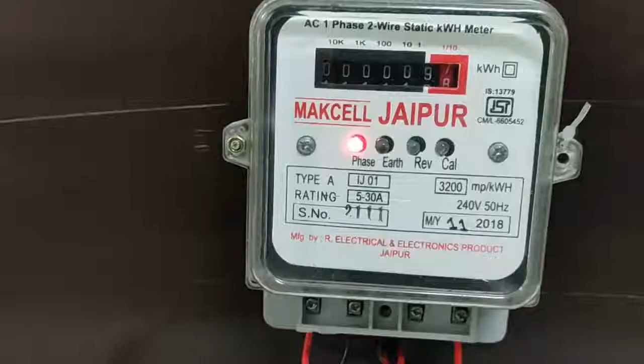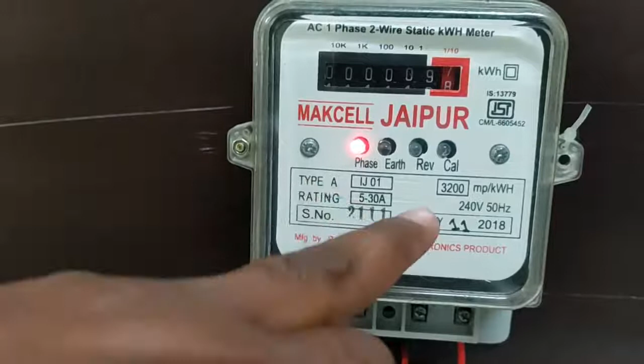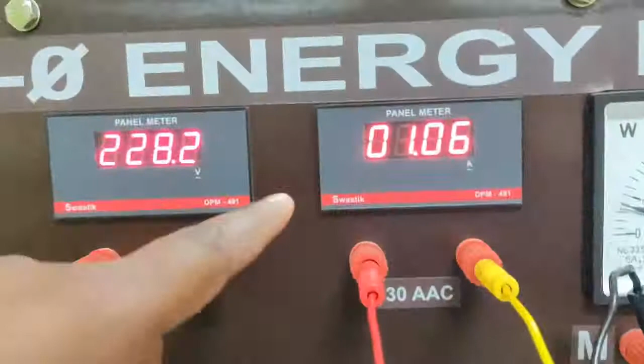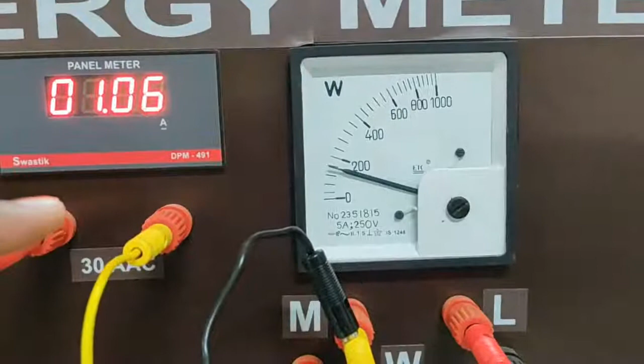Here you can see the number of revolutions LED is not blinking because load is not applied. In order to apply load, you have to switch this terminal, that is the 1 ampere load. You can see the 1 ampere current through the output terminal of the energy meter, and you can see the power measured, which is of the order of 180 watts.